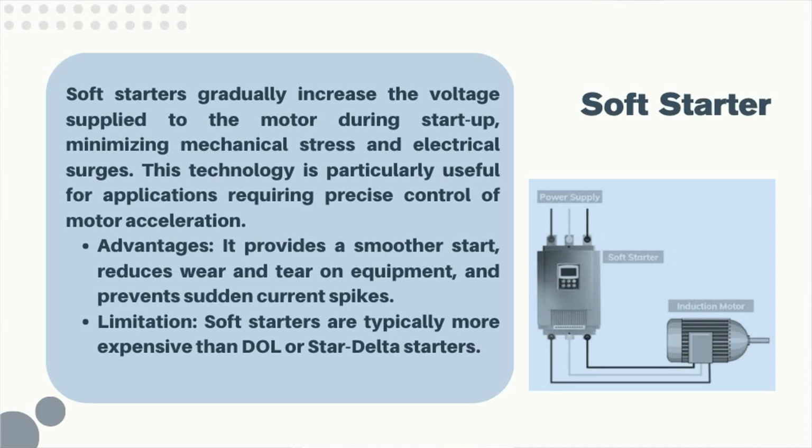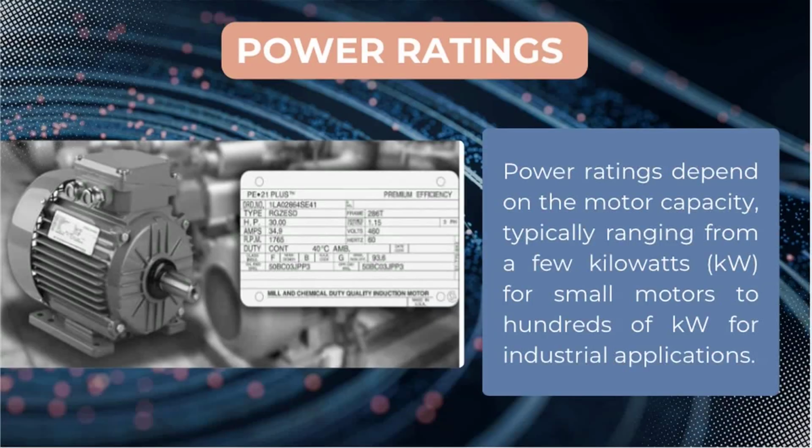Advantages: it provides a smoother start, reducing wear and tear on equipment and prevents sudden current spikes. Limitation: soft starters are typically more expensive than DOL or star delta starters. Power ratings. The power ratings of starters vary based on the motor they are designed to control.